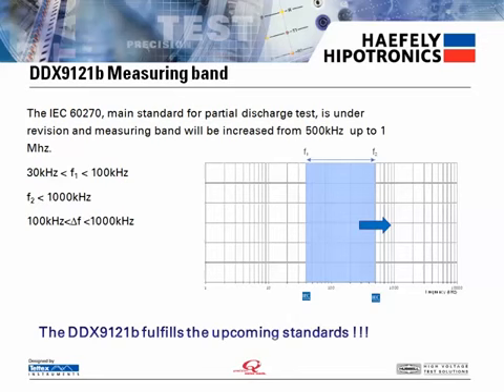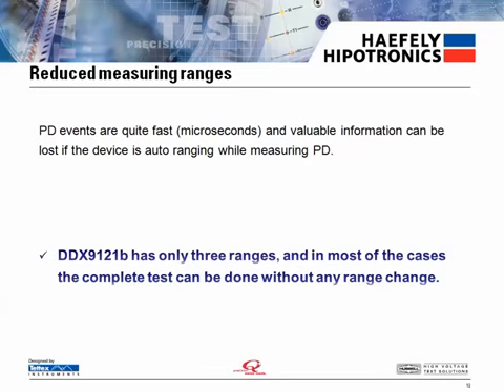The DDX9121B will meet the upcoming changes to IEC 60270, which increases the measuring band from 500 kHz up to 1 MHz. PD events are quite fast, and valuable information can be lost if the detector is auto-ranging while measuring. The DDX9121B only has 3 ranges, and in most cases can test without any auto-ranging.